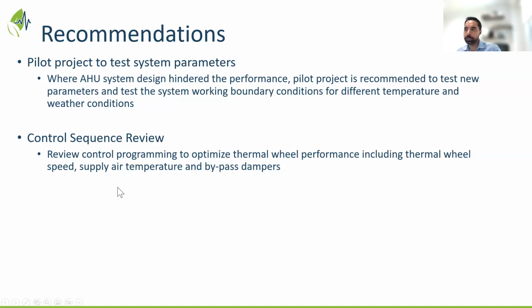Control sequence of operation review is absolutely something that should be done for every system, especially if you're having issues maintaining consistent supply temperatures. It is probably driven by your programming that's not letting you get to your supply temperatures. And sometimes bypass dampers are recommended. Generally, we see in the newer systems there are bypass dampers on the supply and the exhaust side. What we are suggesting is to make them modulating, because you might need them one day. Currently, they're only 2 position. So make them modulating, so you have another variable to control your output for the wheel if you're having issues with your supply temperatures.